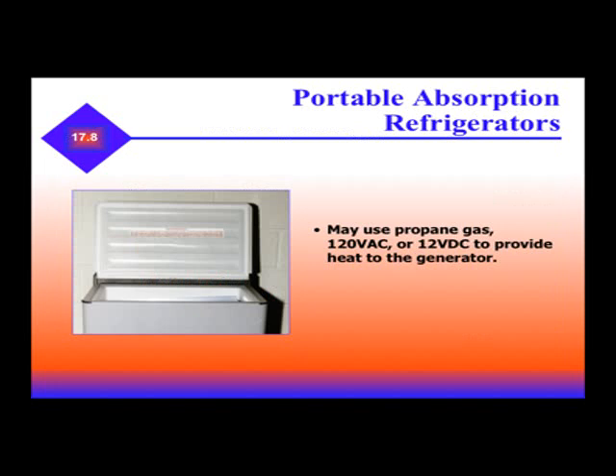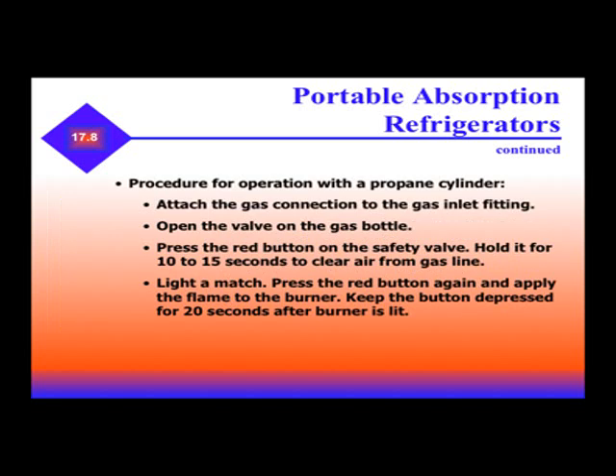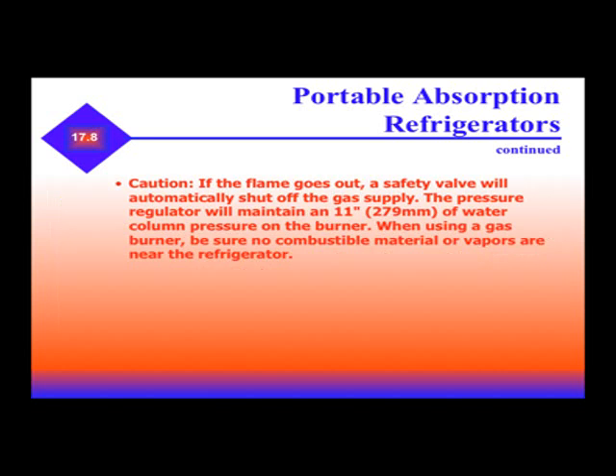Portable absorption refrigerators may use propane gas, 120-volt AC, or 12-volt DC to provide heat to the generator. The pull-down time is 2 to 6 hours depending on ambient temperature. A small propane cylinder provides approximately 70 hours of continuous operation. To operate a propane system: attach the gas connection to the gas inlet fitting, open the valve on the gas bottle, press the red button on the safety valve and hold it for 10 to 15 seconds to clear air from the gas line, light a match, press the red button again and apply the flame to the burner, and keep the button depressed for 20 seconds after the burner is lit. If the flame goes out, the safety valve will automatically shut off the gas supply.